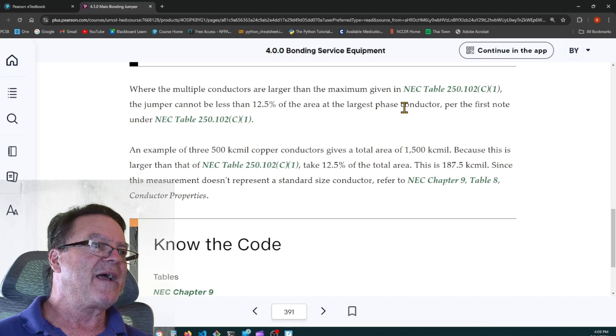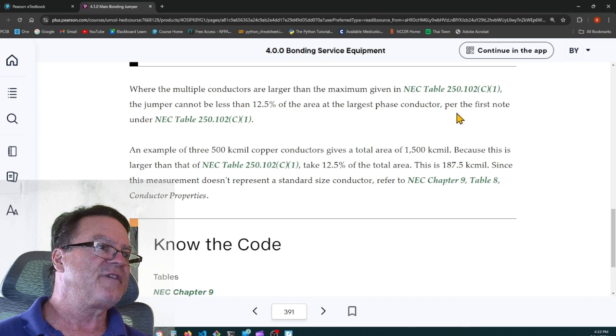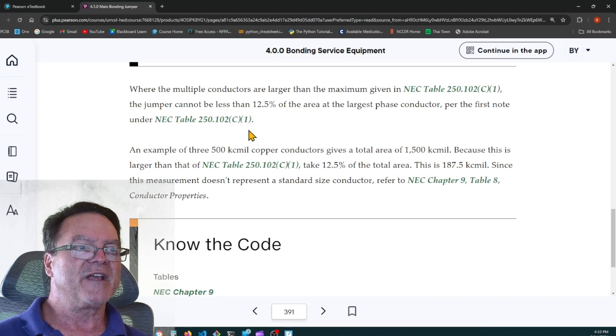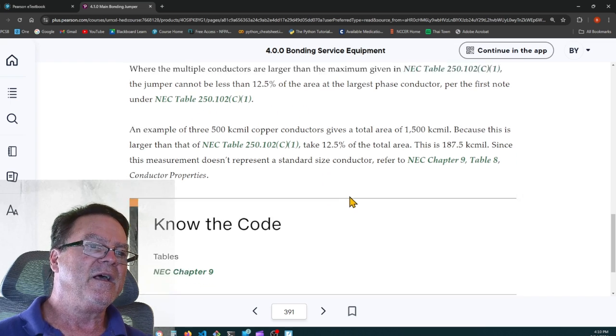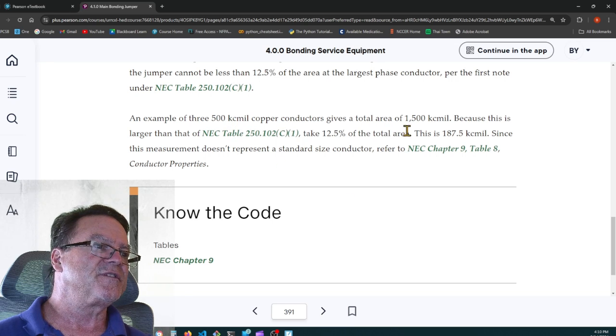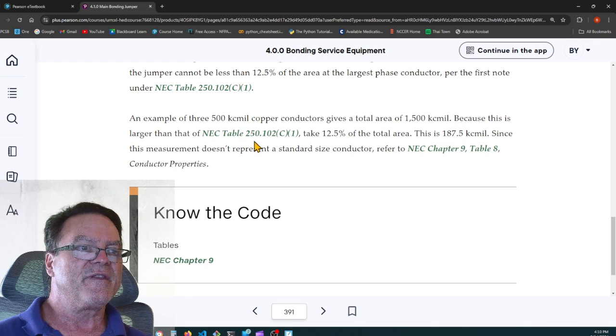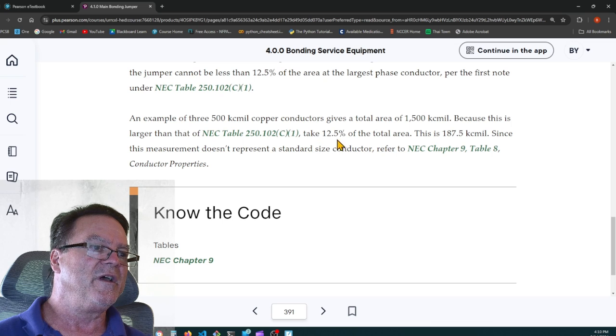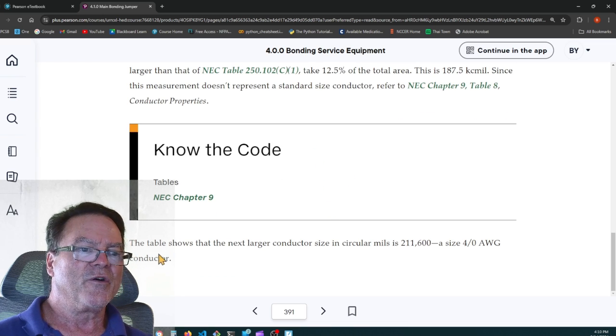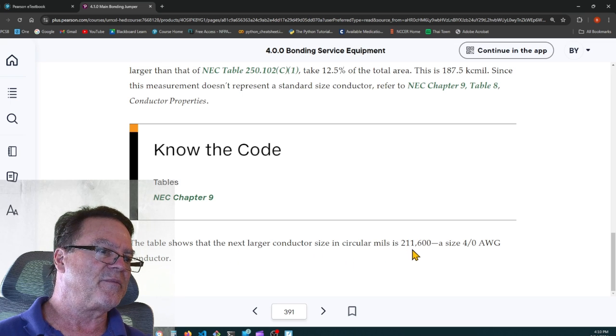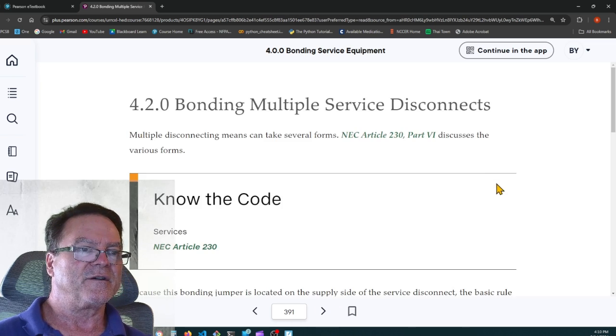Where the multiple conductors are larger than the maximum given in table 250.102C1, the jumper cannot be less than 12.5% of the area of the largest phase conductor per the first note under table 250.102C1. An example of three 500 kcmil copper conductors gives a total area of 1,500 kcmil. Because this is larger than that of NEC table 250.102C1, take 12.5% of the total area. This is 187.5 kcmil. Since this measurement doesn't represent a standard size conductor, refer to Chapter 9, Table 8, Conductor Properties, and go to the next size. The table shows that the next larger conductor size in circular mils is 211,600. It's a size 4-aught. So that's what you'd use for your bonding conductors.